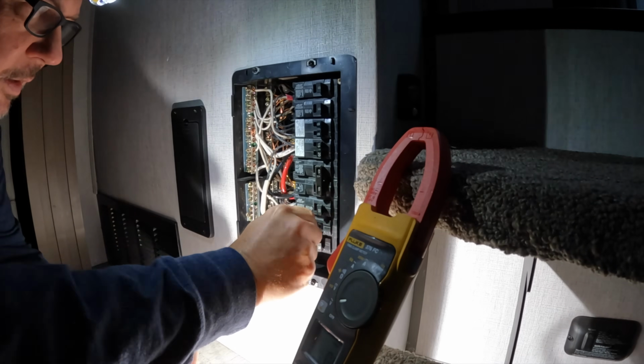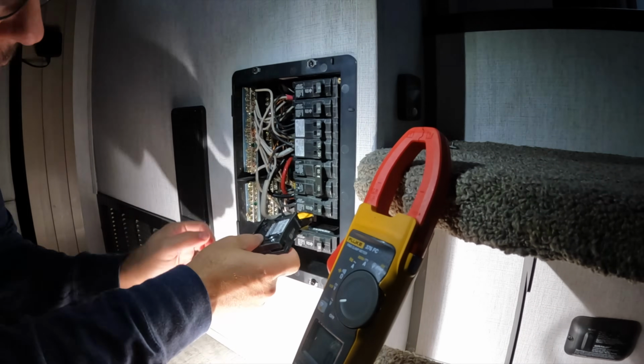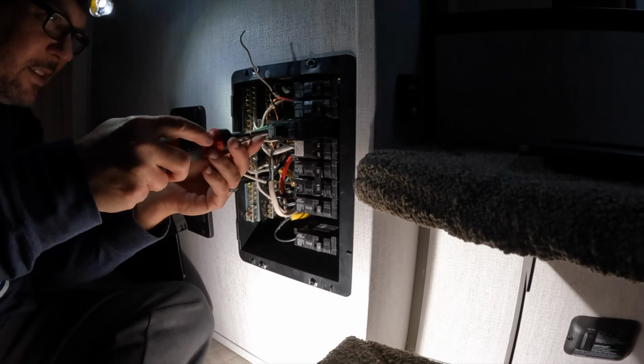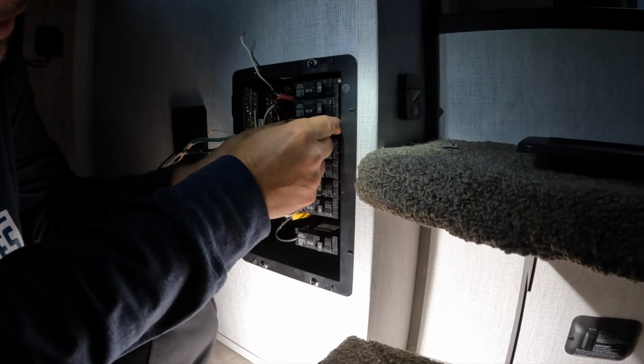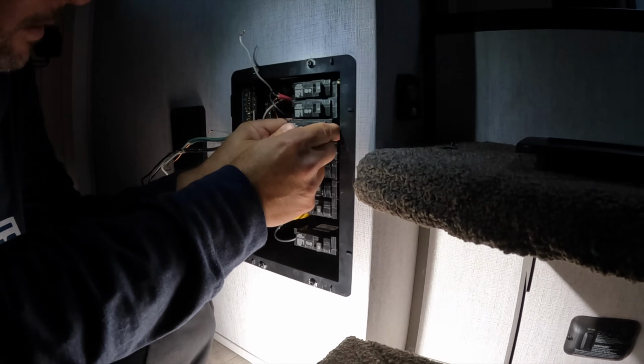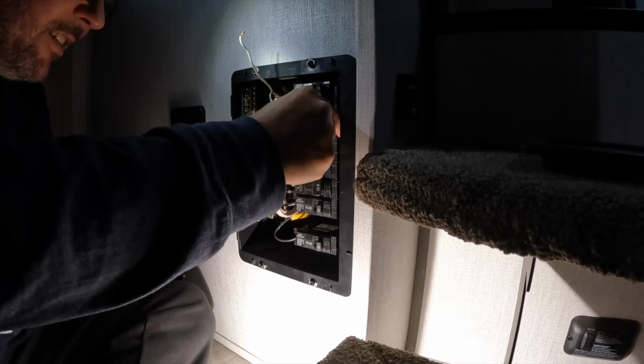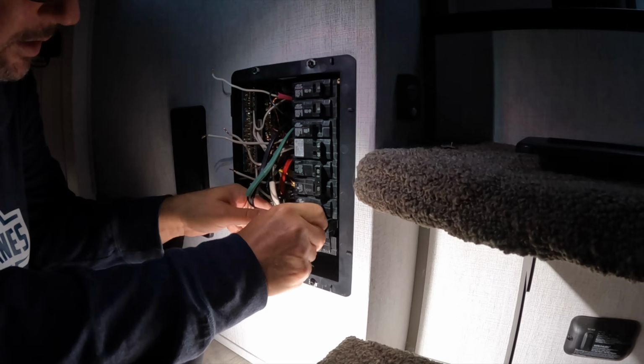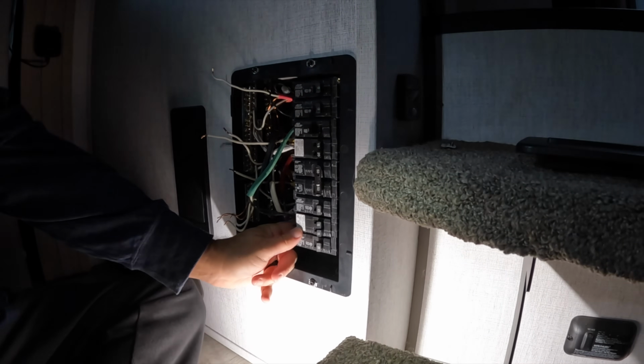So all I did to remedy this was I just moved the bedroom AC, AC2, from line 2 to line 1. Now, if you've ever dealt with your distribution panel in your RV, again, if you haven't or you don't know what a distribution panel is, don't do this. So all I did was I took the AC2 breaker from line 2, moved it up to line 1. Of course, I've got to make room for it. I got to swap something around. And the one that made most sense was a double breaker that was for the microwave and the refrigerator. I'll move those down to line 2.